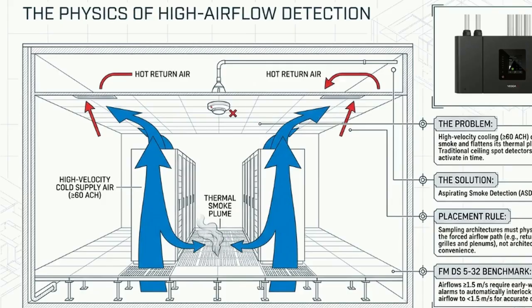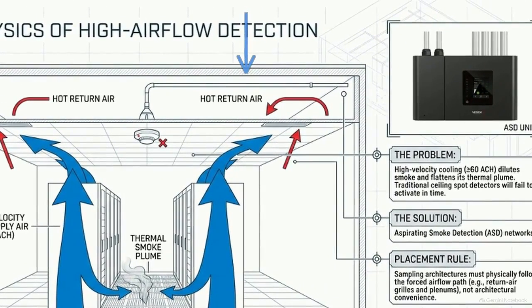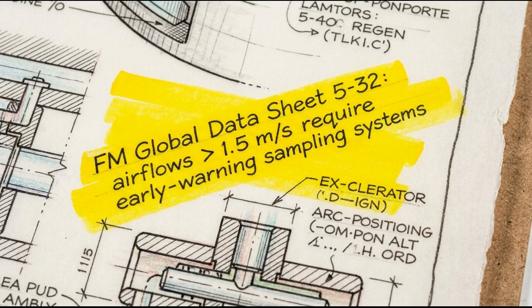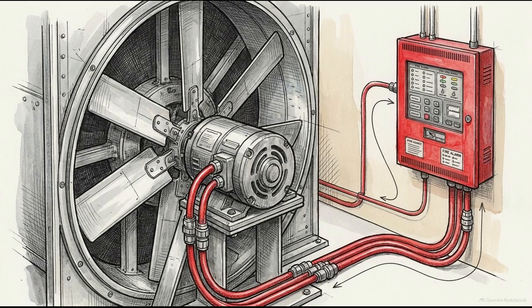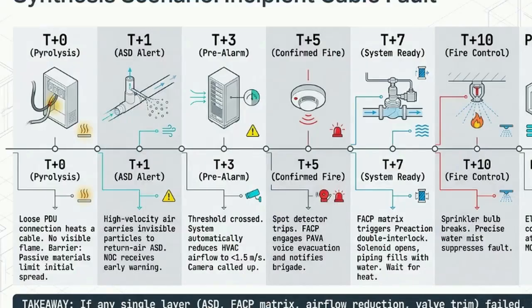As this diagram shows, detection systems must be engineered to physically follow these forced airflow paths directly into the return air grills. Aspirating smoke detection, or ASD networks, constantly sample these return air streams to catch invisible pyrolysis particles the moment they are generated. The FM Global Data Sheet 5-32 benchmark confirms this. Airflows greater than 1.5 meters per second require these early warning sampling systems. Detection must automatically interlock with the HVAC system to reduce airflow, or the active suppression agents will simply be blown away. Moving down the timeline to T+3 and T+5, the system reaches the escalation phase.